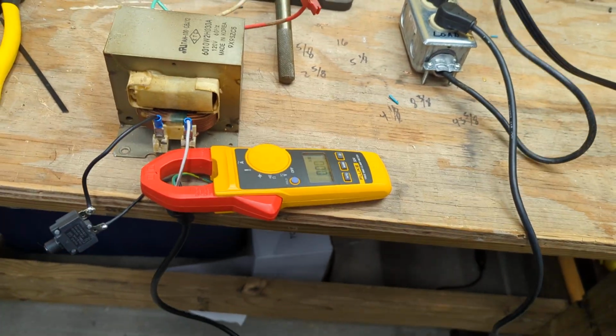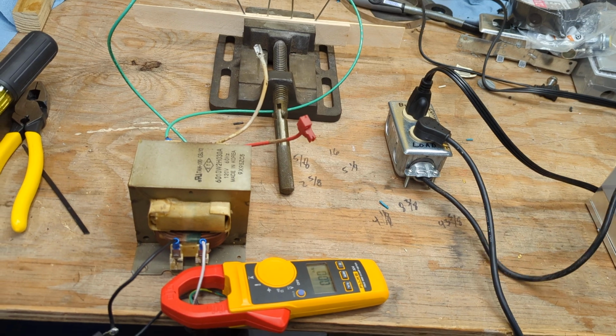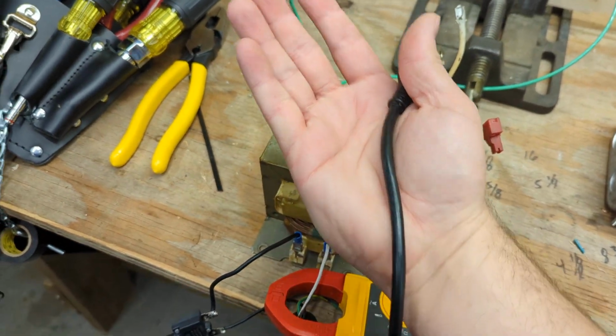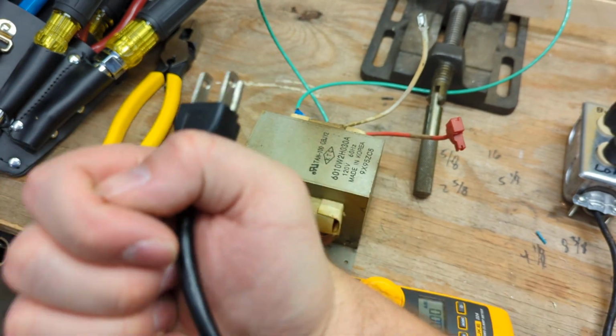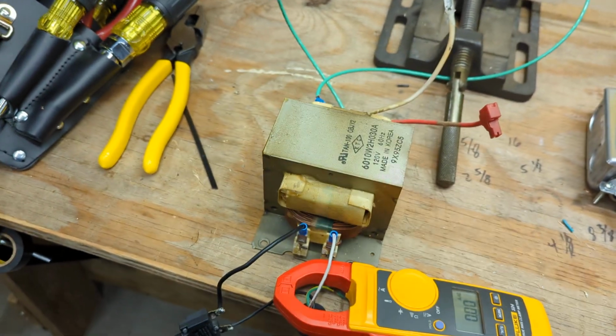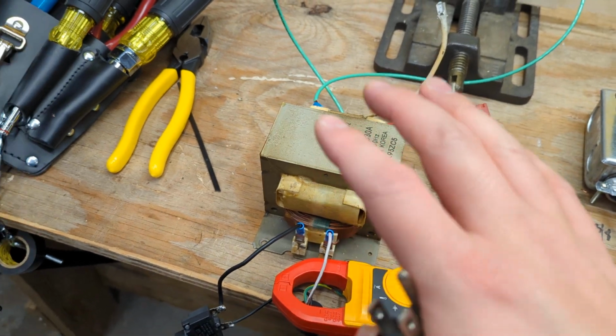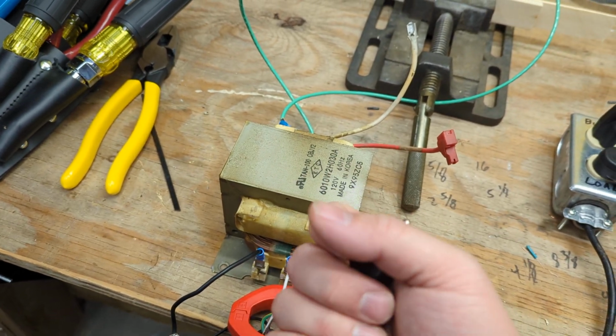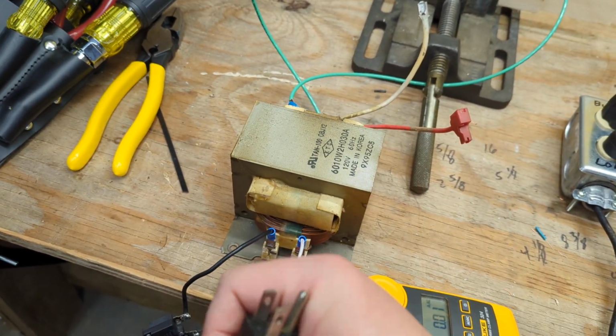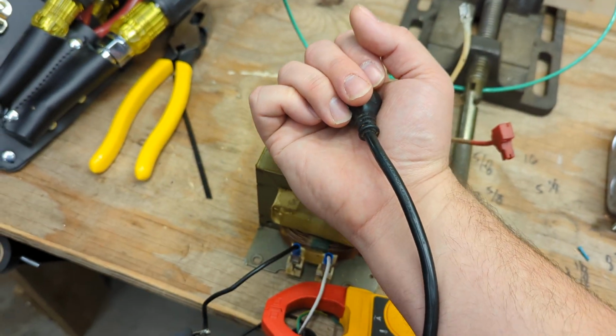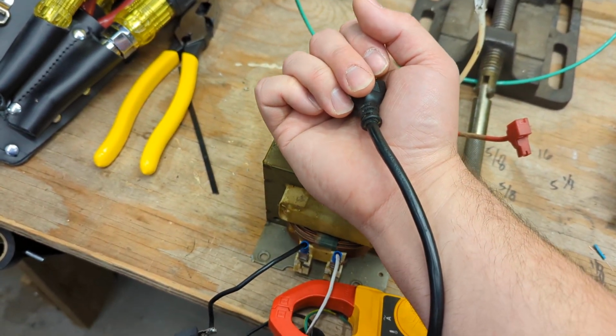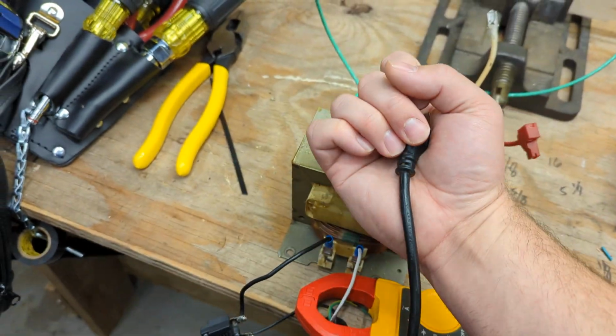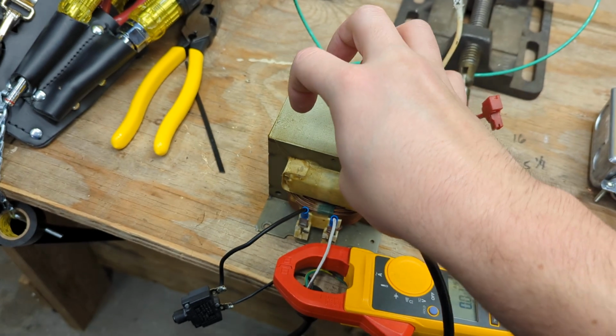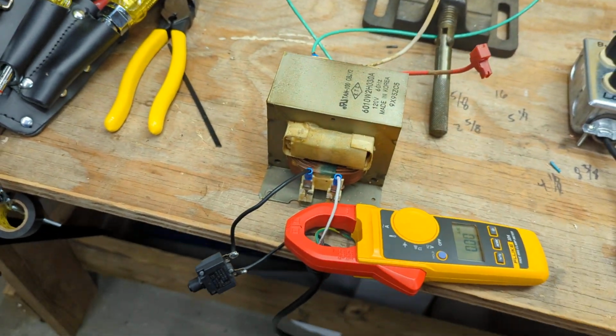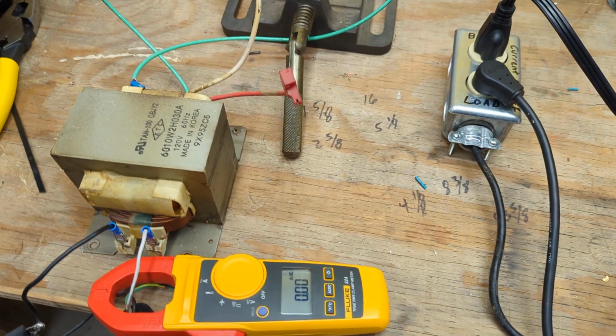I'm holding the cord and validating again that this is the cord we're working with. Let's use the back of the hand, because reflex would be to grab, and using the back of your hand means you'll pull away. I didn't mention that in the last video either. You don't ever grab anything that could be electrically hot, even when checking AC motors. If you work in an industrial environment checking temperature on a motor, never trust that the casing is properly grounded. Use the back of your hand, hover over the device to make sure you won't burn yourself, and you can touch a little. Always use the back of your hand, since the reflex is to pull away, never grip, especially with 277 volts and up, which we're not dealing with here, but it's good practice.